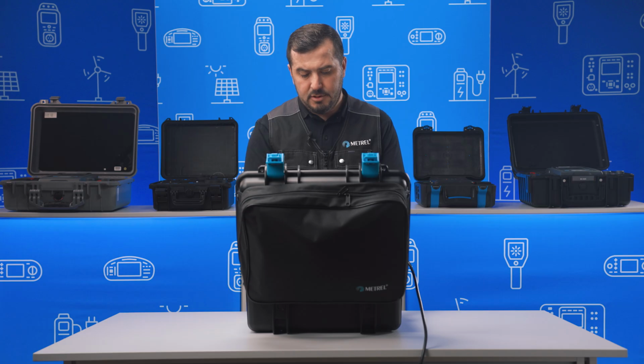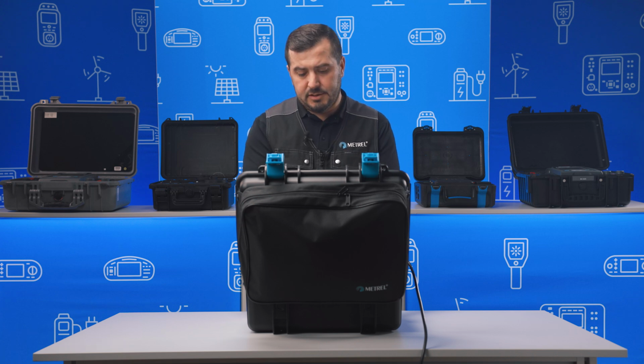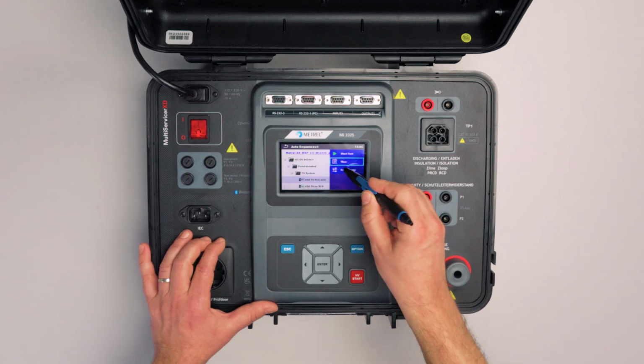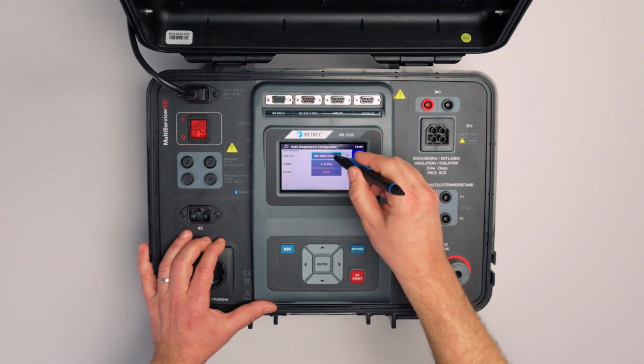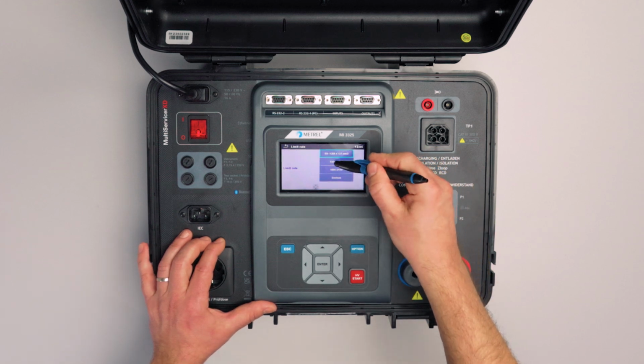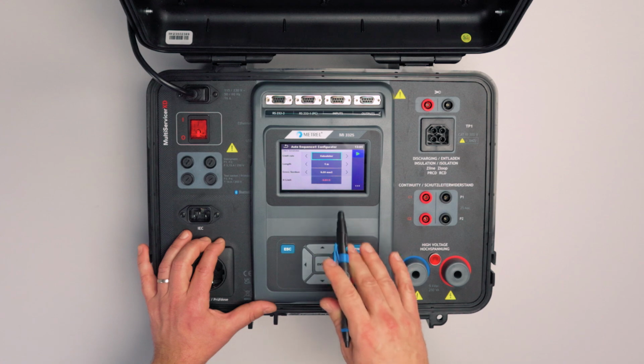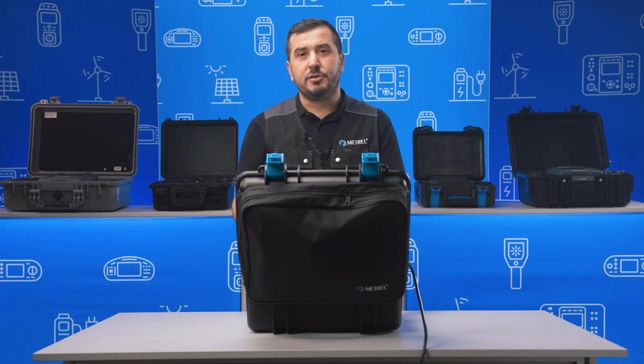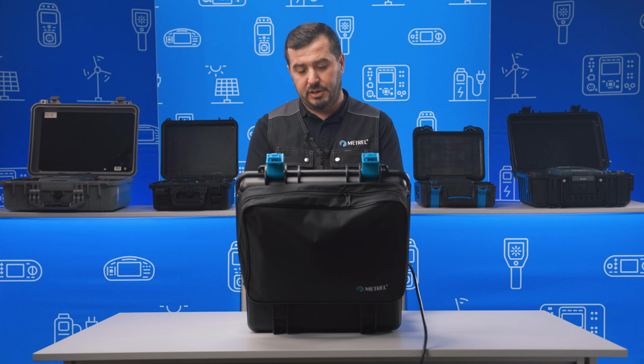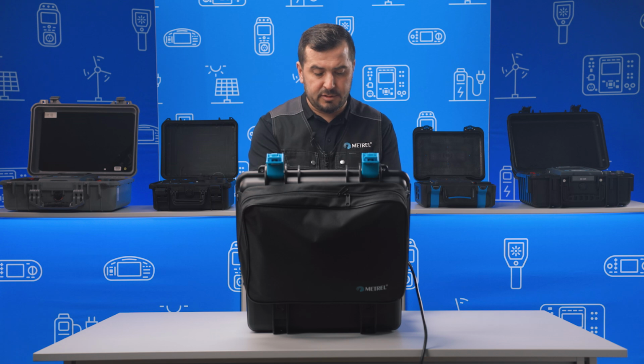What is also a nice feature for the auto sequences is the configurator tool, or in our case the calculator tool, where we can decide to calculate the limit for the earth continuity resistance measurement, which is automatically calculated based on the length and the cross section of the PE conductor measured.